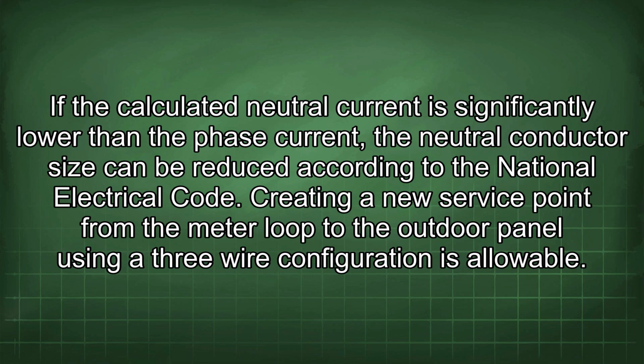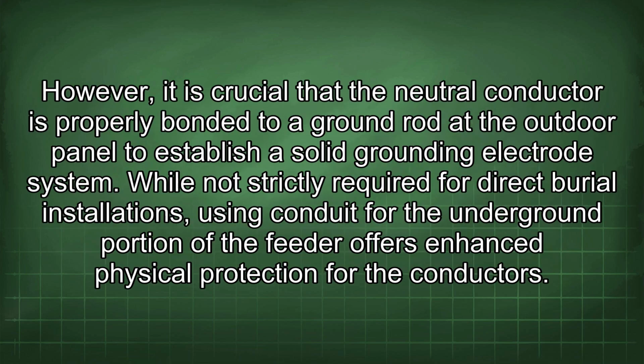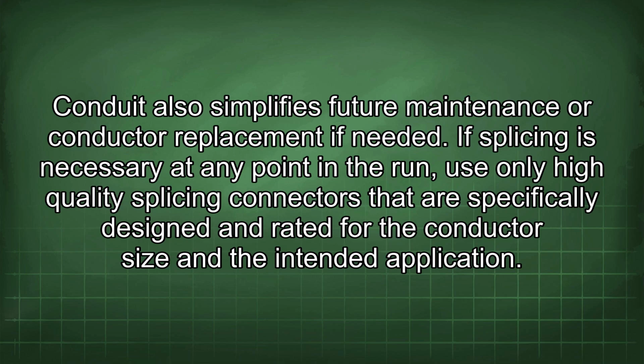Creating a new service point from the meter loop to the outdoor panel using a 3-wire configuration is allowable. However, it is crucial that the neutral conductor is properly bonded to a ground rod at the outdoor panel to establish a solid grounding electrode system. While not strictly required for direct burial installations, using conduit for the underground portion of the feeder offers enhanced physical protection for the conductors. Conduit also simplifies future maintenance or conductor replacement if needed.